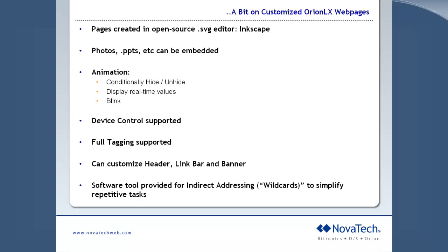We also created a software tool a lot of you are going to enjoy, called indirect addressing. It's a version of a wildcard that lets you design a screen one time if it needs to be used a number of times. For instance, if you have a substation with 15 feeders, each with a 351S, and you want a zoom screen for those 351Ss, instead of creating that screen 15 times with all the links, which can be 80 to 100 links, you create it once and use a wildcard.